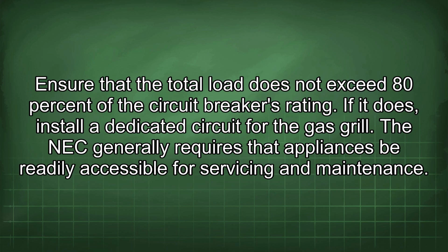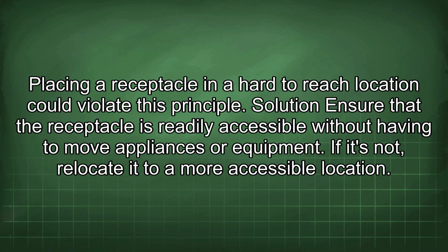Ensure that the total load does not exceed 80% of the circuit breaker's rating. If it does, install a dedicated circuit for the gas grill. The NEC generally requires that appliances be readily accessible for servicing and maintenance. Placing a receptacle in a hard-to-reach location could violate this principle. Solution: ensure that the receptacle is readily accessible without having to move appliances or equipment. If it's not, relocate it to a more accessible location.